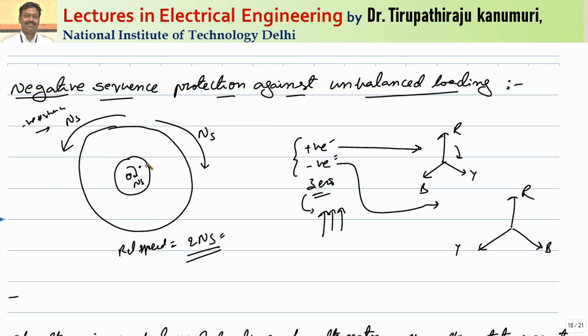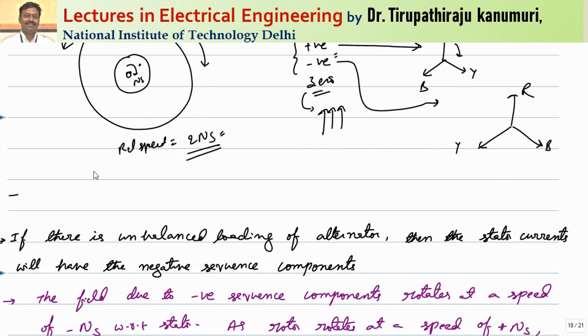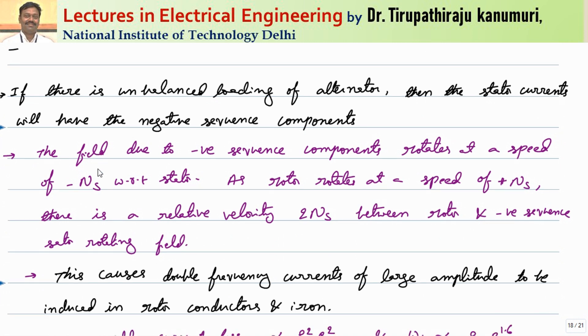The rotor core will experience two types of losses: hysteresis loss and eddy current loss. Both depend on the frequency of magnetic reversals. In this case, because the stator negative sequence field rotates at ns and the rotor rotates at ns in the opposite direction, the relative speed is 2ns, meaning the frequency of hysteresis and eddy currents is two times the normal frequency. Because of this, both losses increase significantly.